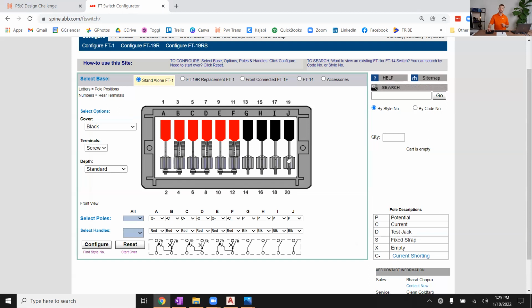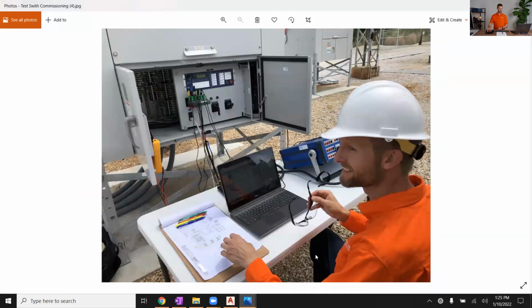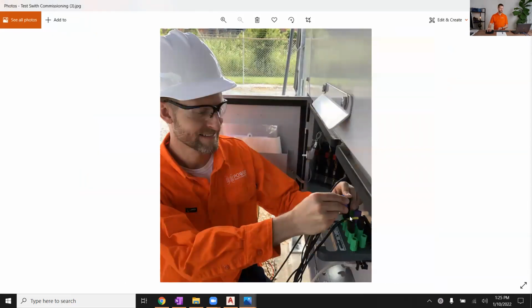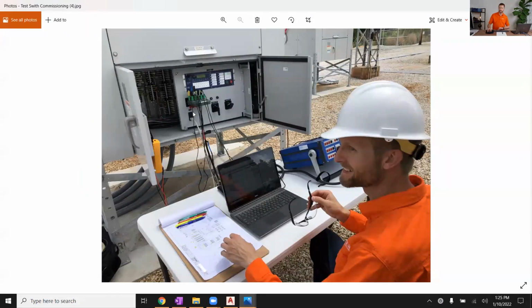And then you'd have VA, VB, VC, and VN on your potentials here. So you inject, or simulate, an overcurrent condition with your test set, for example. And like I was showing you over here, these wires are carrying simulated voltages and currents, not real life power system voltages and currents. You can also wire a trip signal out of your relay back to the test set to confirm that it issued a trip properly when it should have, and to confirm what the time was that the trip was issued, that it was expecting based on maybe an inverse time overcurrent curve, et cetera. Maybe a distance relay time delayed element, zone 2, et cetera. We've talked about these concepts in previous courses. That's not what we're after in this course, but that's kind of the intent of a test switch.